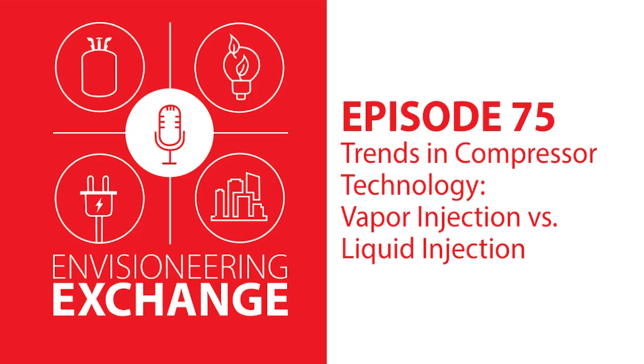There's a couple different ways to do it when we talk about vapor injection. If you get into the components a bit more, a typical vapor injection economizer would have, of course, your economizer, which would be in this case a braze plate heat exchanger or microplate heat exchanger. You would have an expansion valve. You would have pressure and temperature sensors. And then, of course, some interconnecting piping. And then you may have a solenoid valve for shutoff as well. But as you mentioned, basically we're taking the feed coming out of the condenser, going to the economizer.